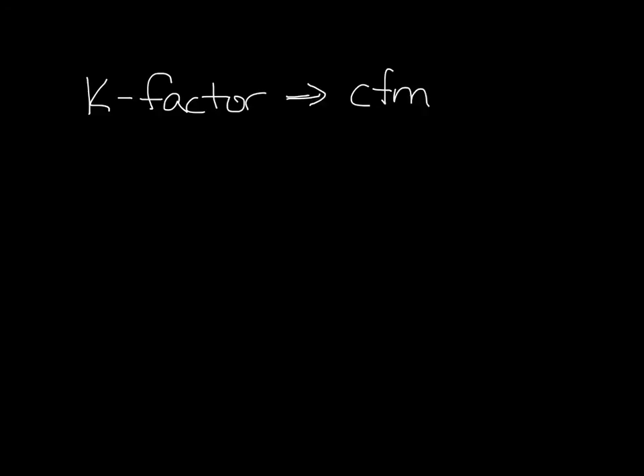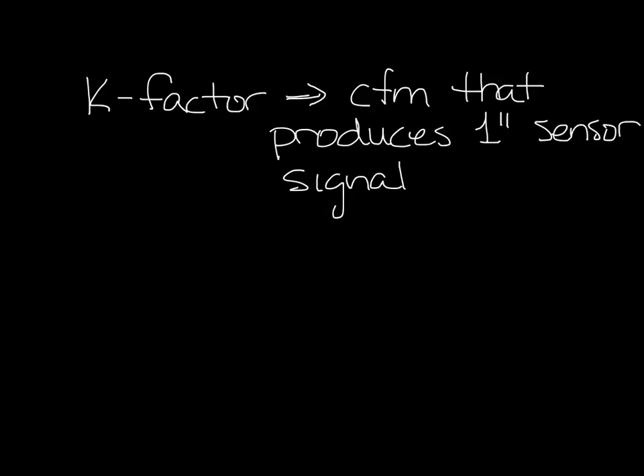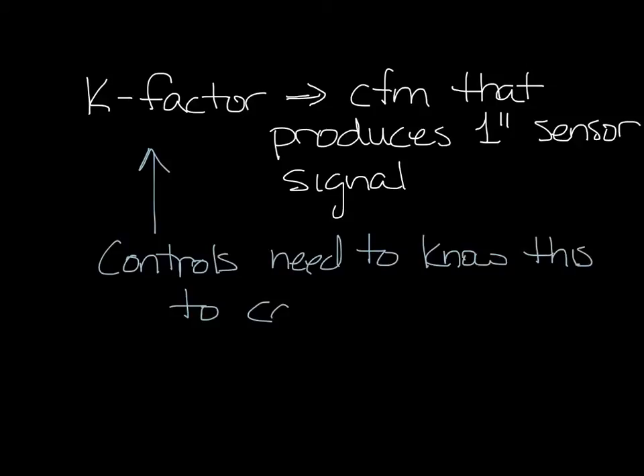The K-Factor is the CFM that will produce a 1-inch sensor signal with that flow sensor at the pressure transducer. This CFM is different for different sensor designs and different sizes. So for the controls on the VAV box to calculate what the airflow going through the box is, it needs to know what the K-Factor of the box is. These K-Factors are entered when the box controls are programmed.